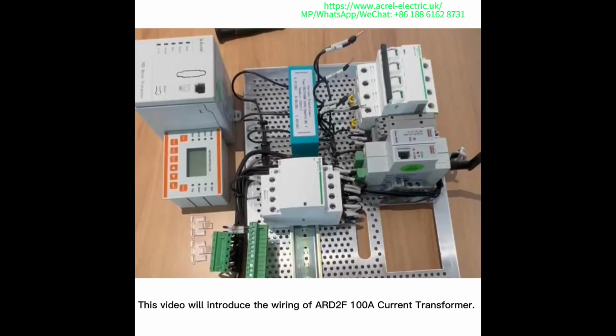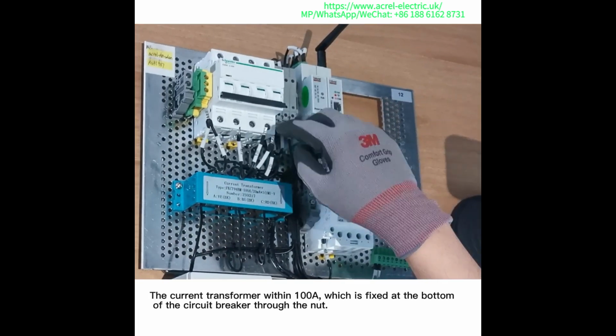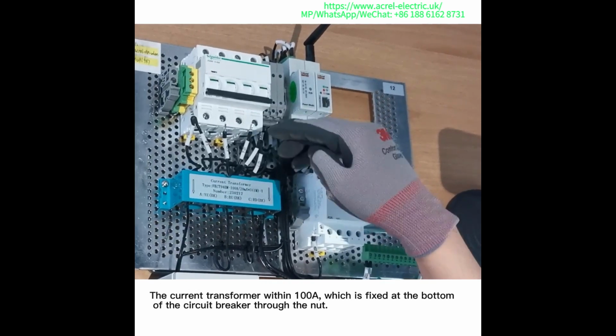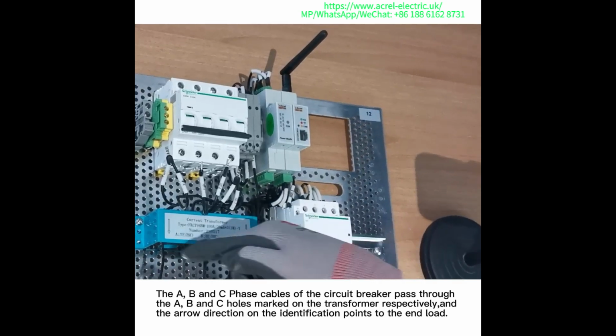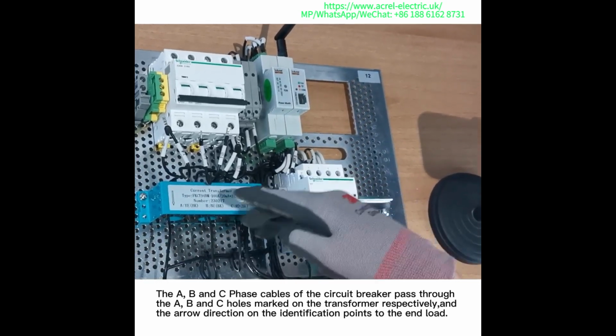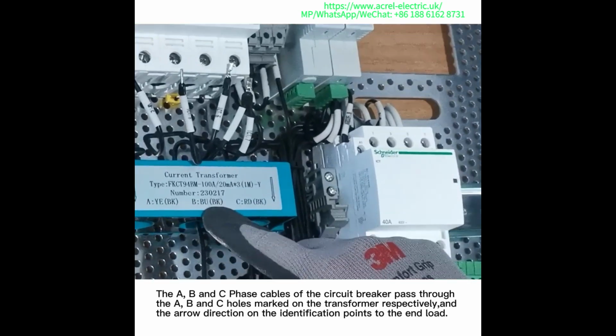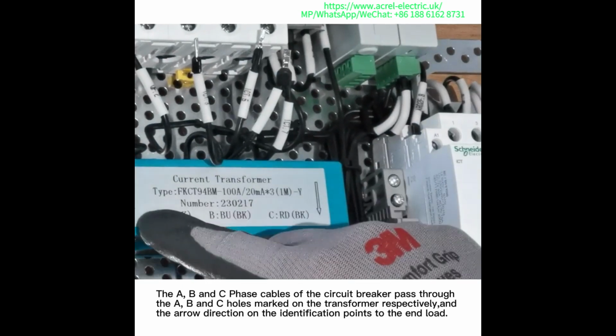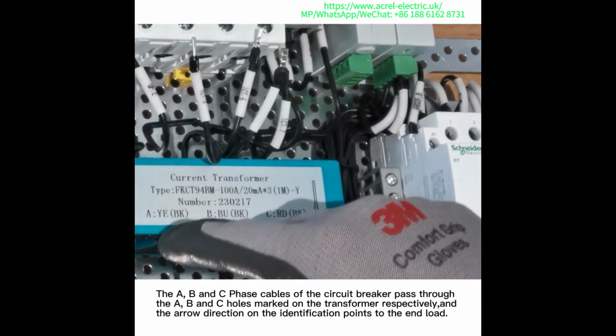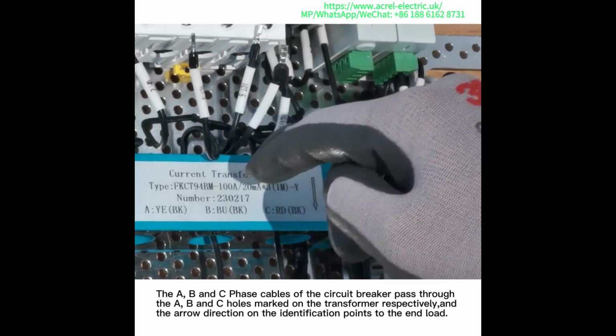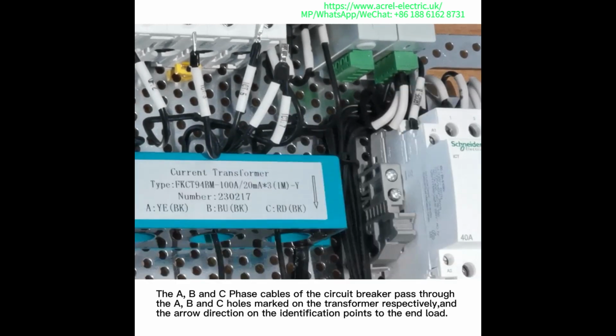This video will introduce the wiring of ARD2F 100A current transformer. The current transformer within 100 ampere is fixed at the bottom of the circuit breaker through the nut. The A, B and C phase cables of the circuit breaker pass through the A, B and C holes marked on the transformer respectively, and the arrow direction on the identification points to the end load.